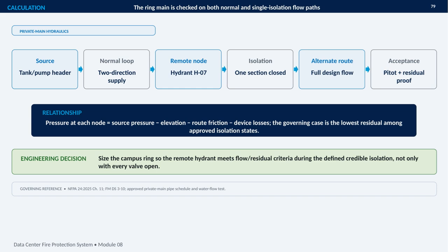That is why the engineering decision is to size the campus ring around the remote hydrant requirement during the defined credible isolation.